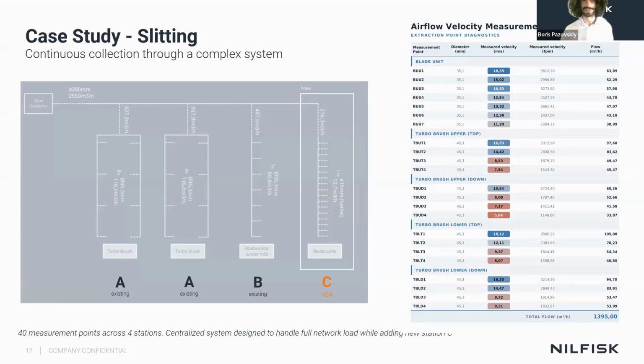every single pickup point. For anybody that knows anything about vacuums, or even if you don't, typically the point closest to the vacuum is going to have the most suction. The last point, so at the C section here, will have the least vacuum. So how do you balance it for a customer to have the same pickup velocity, the same airspeed at each pickup point? Well, you have to size the vacuum the right way.